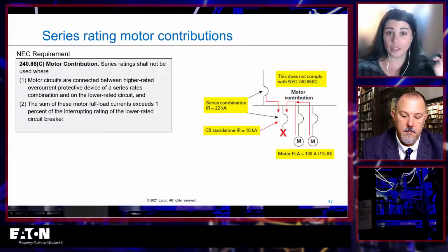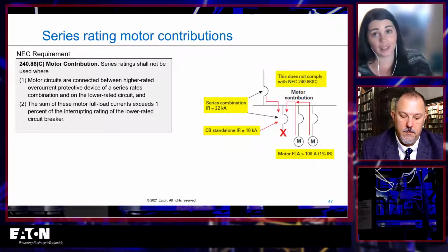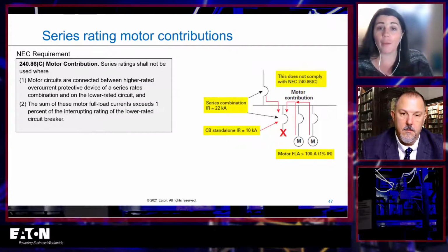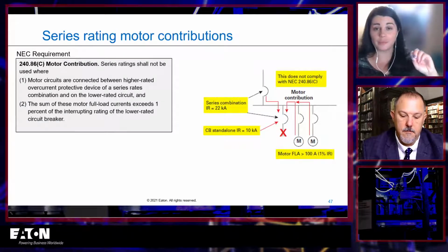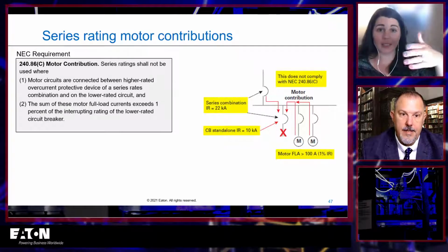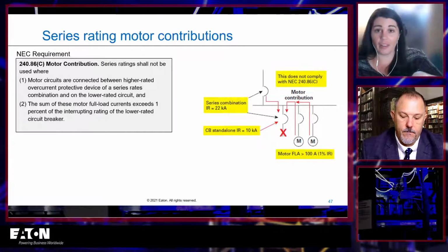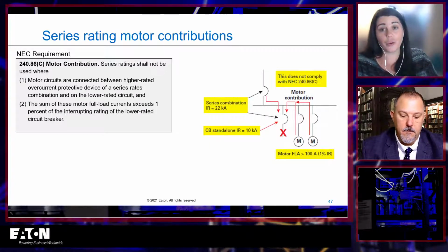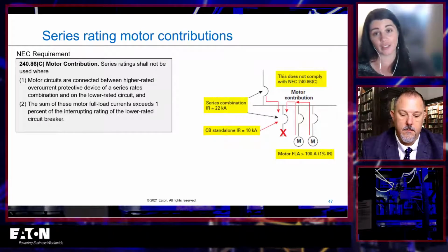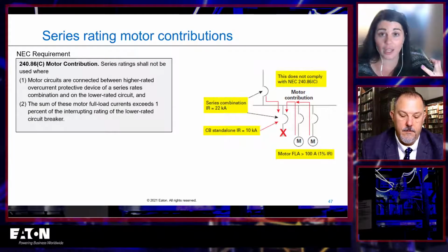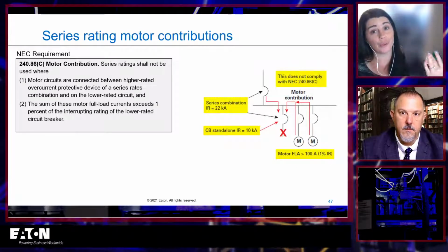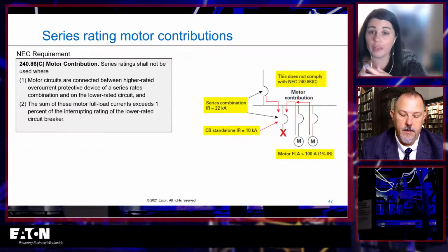if they go to motors and the motor FLA adds up to more than 1% of the interrupting rating of that branch breaker that we are series rating, then you can't apply it. So in this example, we've got 10 kA on there. 1% of 10,000 is 100. If the full load amps of all of my branch devices wind up being more than 100 amps, I cannot series rate this. This is why series ratings you typically only see on things like lighting panel boards where there are no motors involved, because this is a very, very limiting part.